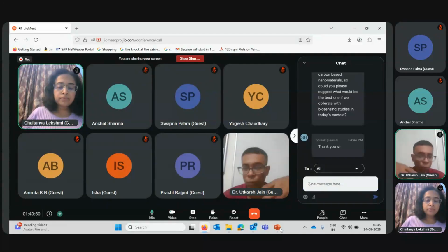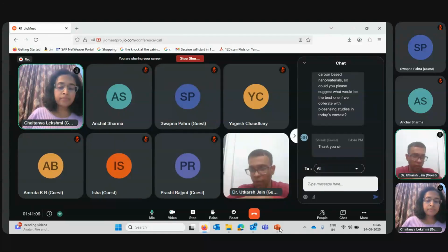Now in glucose sensors, where glucose oxidase is used, people are facing this problem. So what they have done in the glucose biosensor is coat the enzyme on the working electrode, and over the enzyme they have made a layer of mesh work so that the enzyme does not go out of the strip; they entrapped the enzyme on the surface.